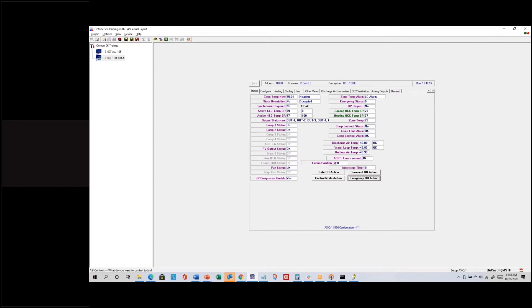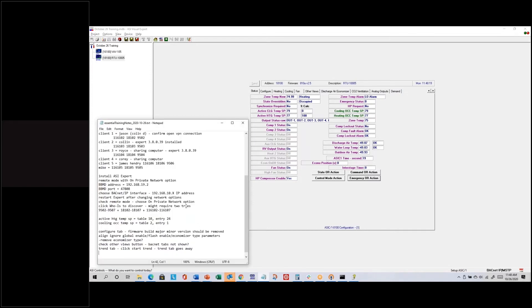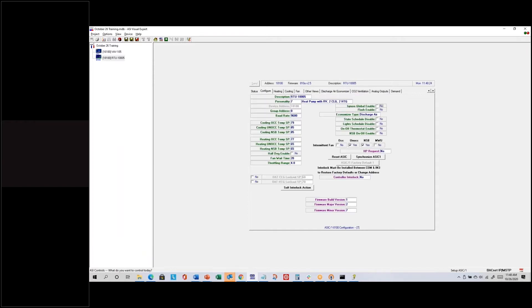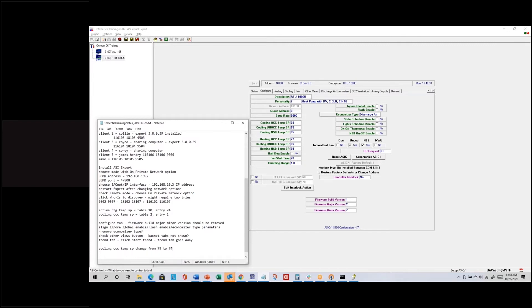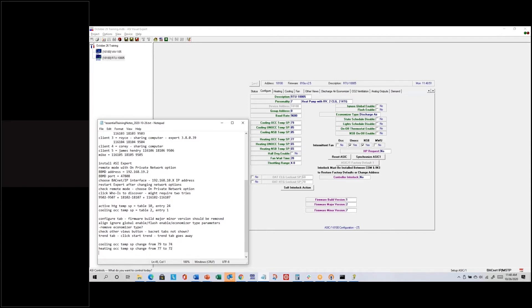What I saved has everything that's currently in this controller. I'm going to change the Cooling OCC Temp SP from 79 to 74, and I'll change the Heating OCC Temp SP from 77 to 72, just to show that when I reload, those values will change. I'm also going to change the description from RTU 1005 to HP 1005.